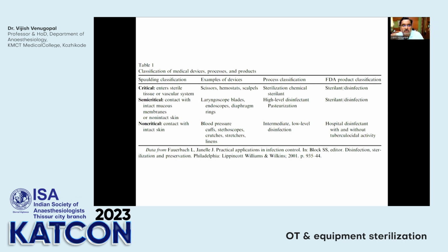So there is a classification that is called the Spalding classification. It divides these medical devices into three groups: critical, semi-critical, and non-critical. Critical means these devices enter the sterile tissue or the vascular system, like the scissors, scalpels, or your Seldinger needle for putting a central line. The semi-critical ones are those which contact intact mucous membranes or non-intact skin, like your laryngoscope blades, the endoscopes, the TE probes, your bronchoscope. All that comes under semi-critical devices. The non-critical ones contact the intact skin, like your blood pressure cuff, the stethoscopes, and the linen that you use on the patient.